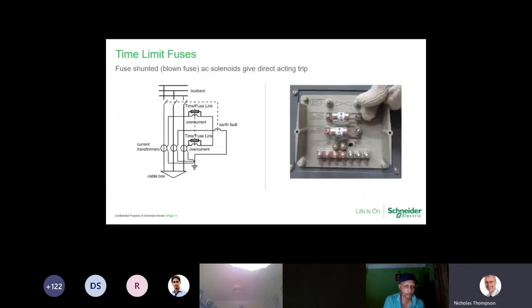When you start to look at the protection, it is incredibly simple. It's very simple to see, it's very simple to replace, and the actual schematic that we've got there is relatively simple compared to primary distribution. You've got your protection CTs. They ultimately will power the trip coils. We've got 3 trip coils, and we've got, showing there, 2 fuses which are in parallel.